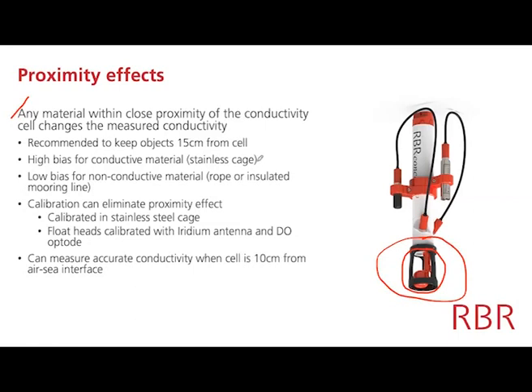If you introduce a piece of bare mooring wire or a stainless protective cage, they're going to bias the conductivity high, and that's just because metal, steel for the most part, is more conductive than seawater. If you have an insulated mooring line or any other kind of non-conductive or poorly conductive material, a piece of rope, you may bias the measurement low, because those materials are poor conductors relative to seawater. And as I mentioned before, this is only a problem if you haven't calibrated the instrument with these objects nearby.